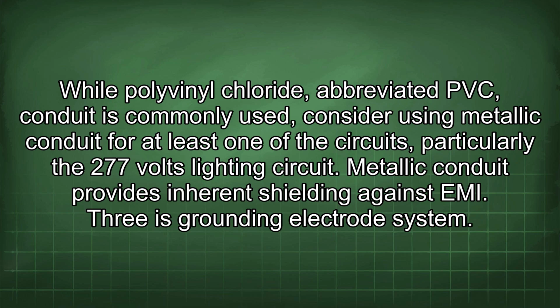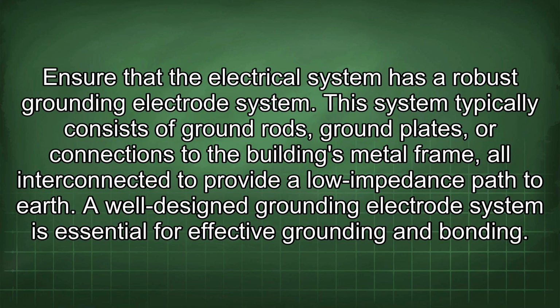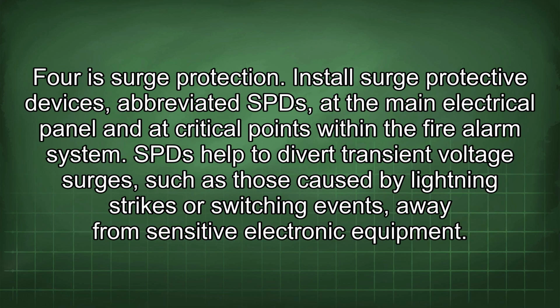Three is grounding electrode system. Ensure that the electrical system has a robust grounding electrode system. This system typically consists of ground rods, ground plates, or connections to the building's metal frame, all interconnected to provide a low impedance path to earth. A well-designed grounding electrode system is essential for effective grounding and bonding. Four is surge protection. Install surge protective devices, abbreviated SPD, at the main electrical panel and at critical points within the fire alarm system. SPD help to divert transient voltage surges, such as those caused by lightning strikes or switching events, away from sensitive electronic equipment.